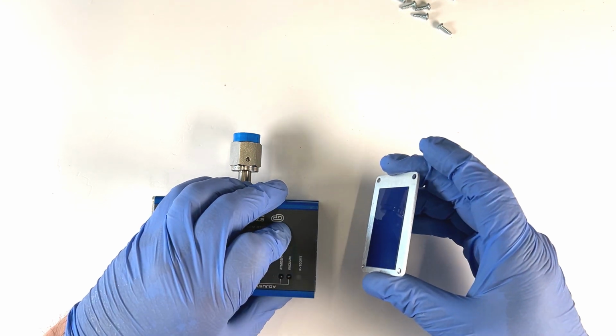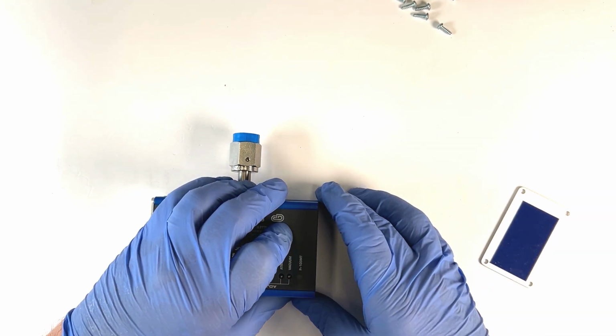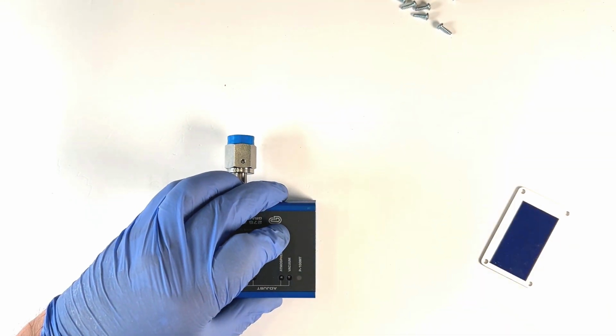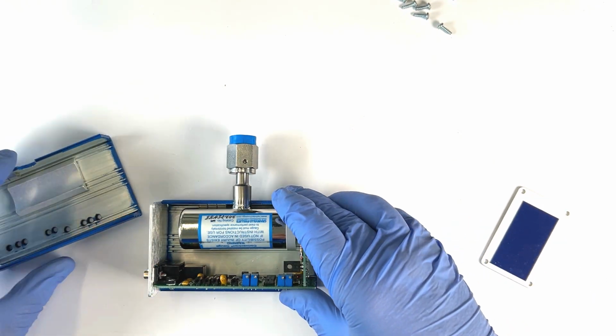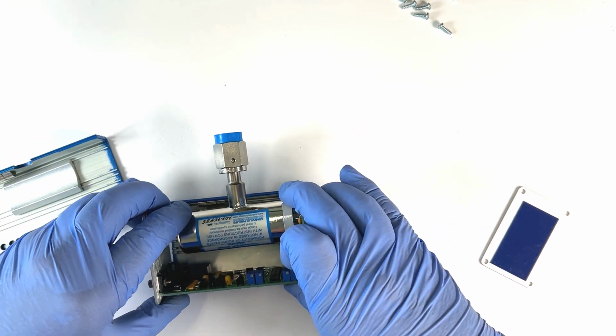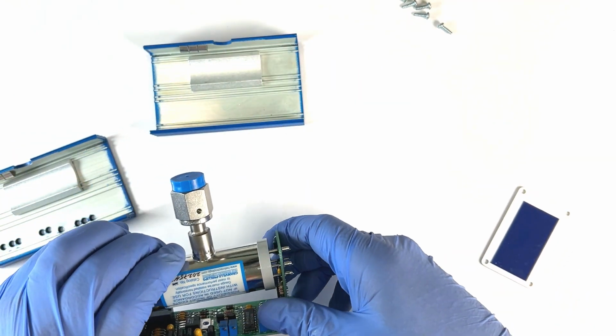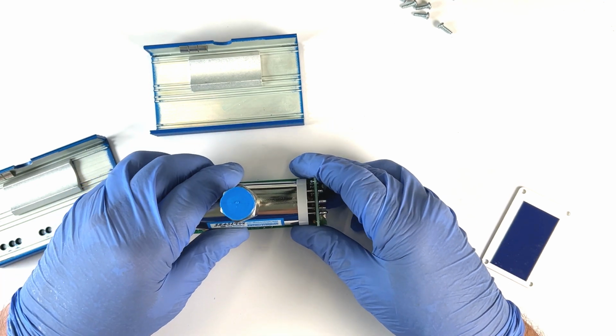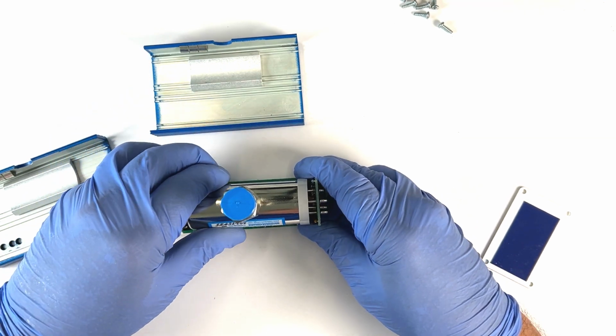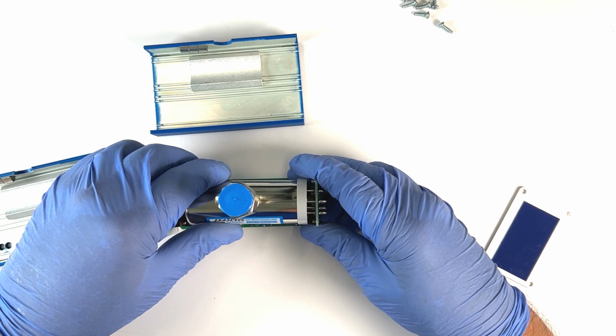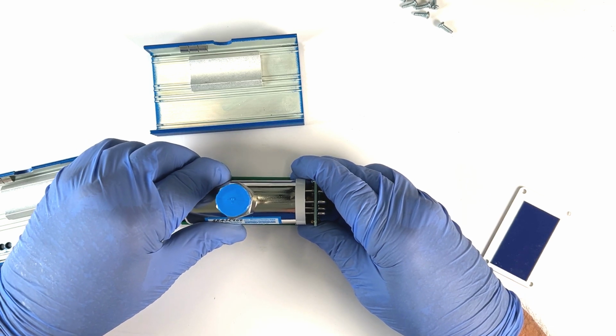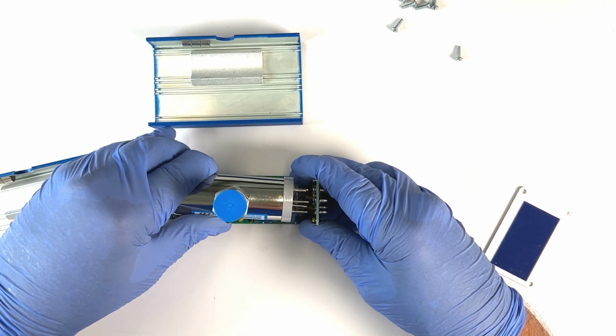Remove the end plate that does not have a connector. Then remove both sides of the blue housing to access the gauge internal. Carefully unplug the Convectron gauge from the spring-loaded sockets in the printed circuit board by gently pulling out.